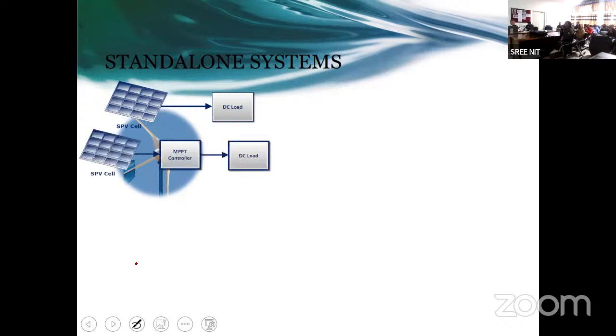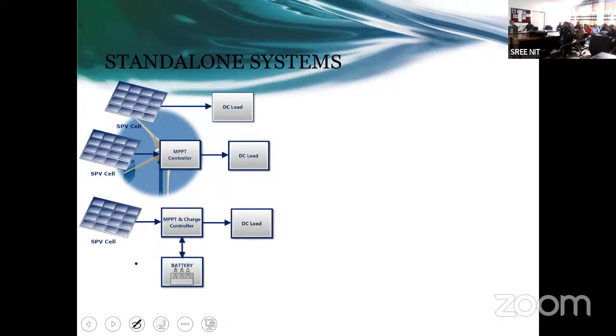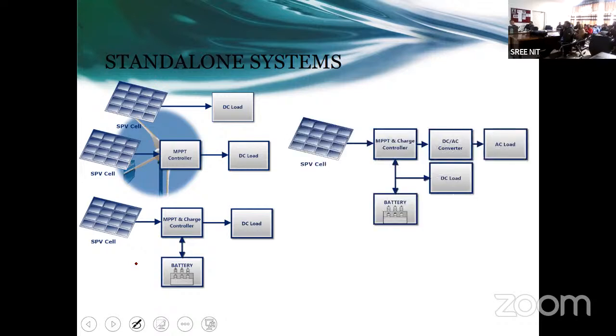You can have an MPPT control algorithm in between just to have maximum power generation from there. And then you can have a small battery backup also connected to meet the fluctuations or to enhance the reliability of the supply. So that thing is also possible. And then a small DC load as well as an AC load can be fed. So a DC AC inverter can also be installed inside the system. So all those things become a standalone system where different sources and different battery backups may be there. AC load can be fed, DC load can also be fed simultaneously.